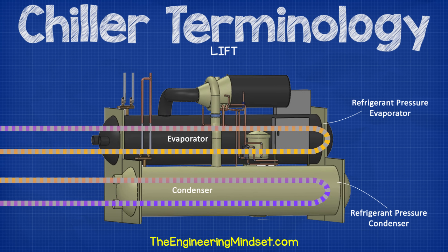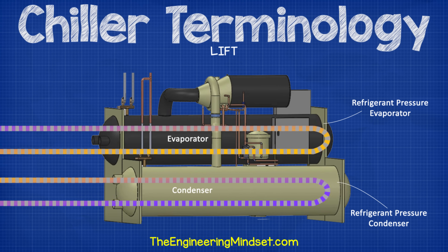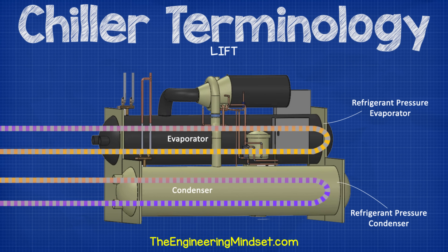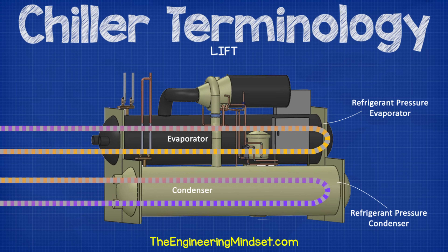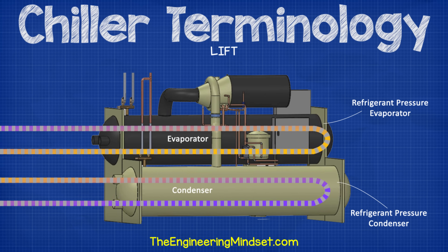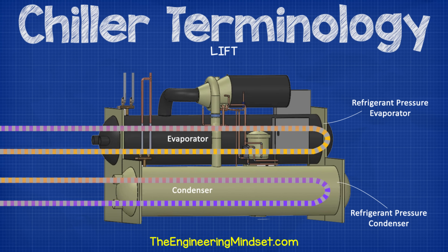Lift. Lift refers to the difference in pressure between the refrigerant in the condenser and the refrigerant in the evaporator. The higher the difference, the more work the compressor is having to do in order to achieve this. The chilled and condenser water temperatures and the approach temperatures set the required lift. Reducing the condenser water set point and increasing the chilled water set point will reduce the energy consumption of the compressor.